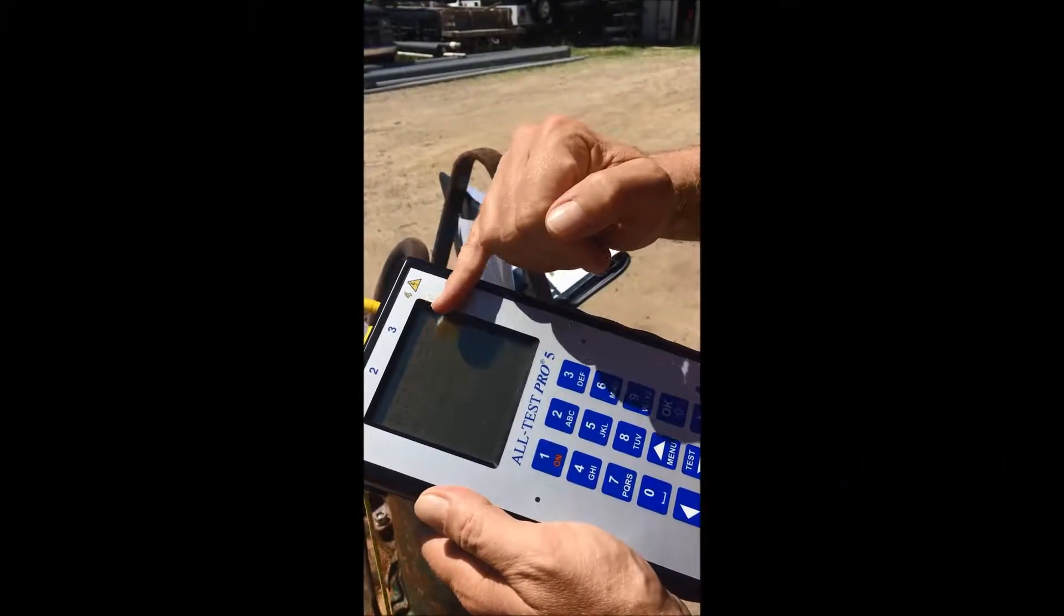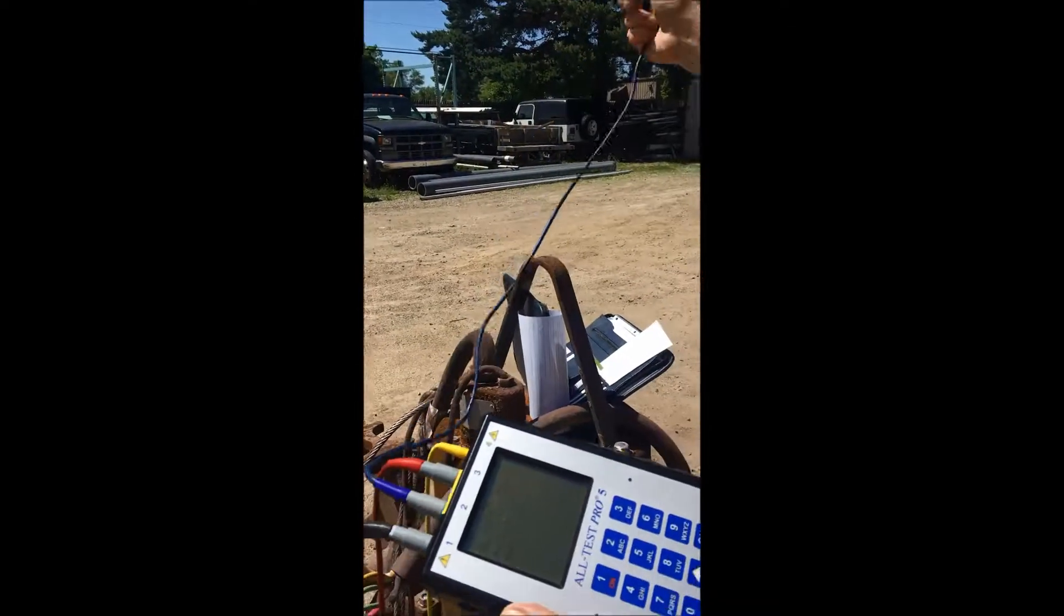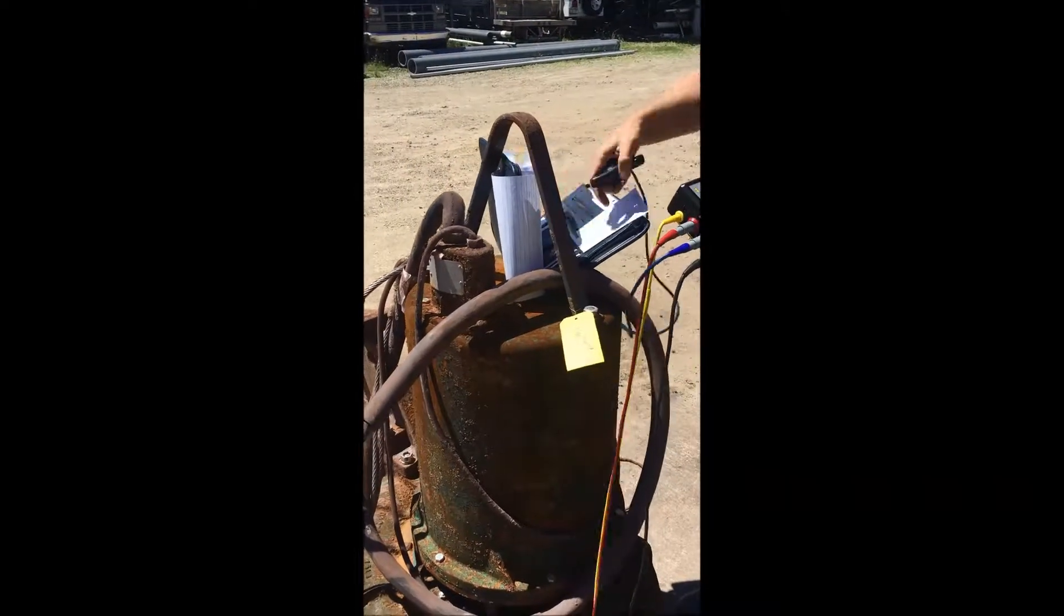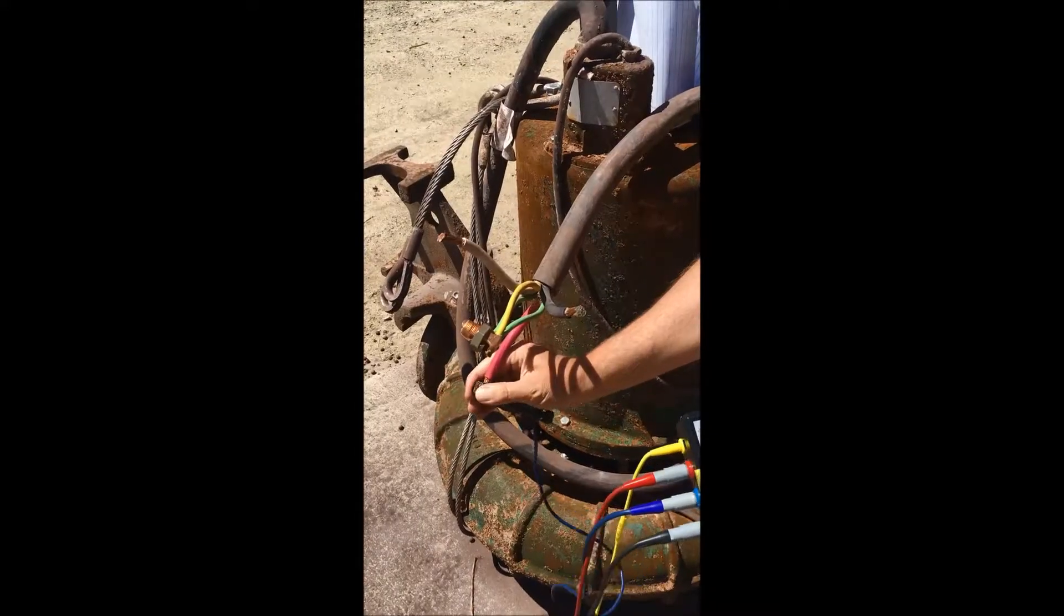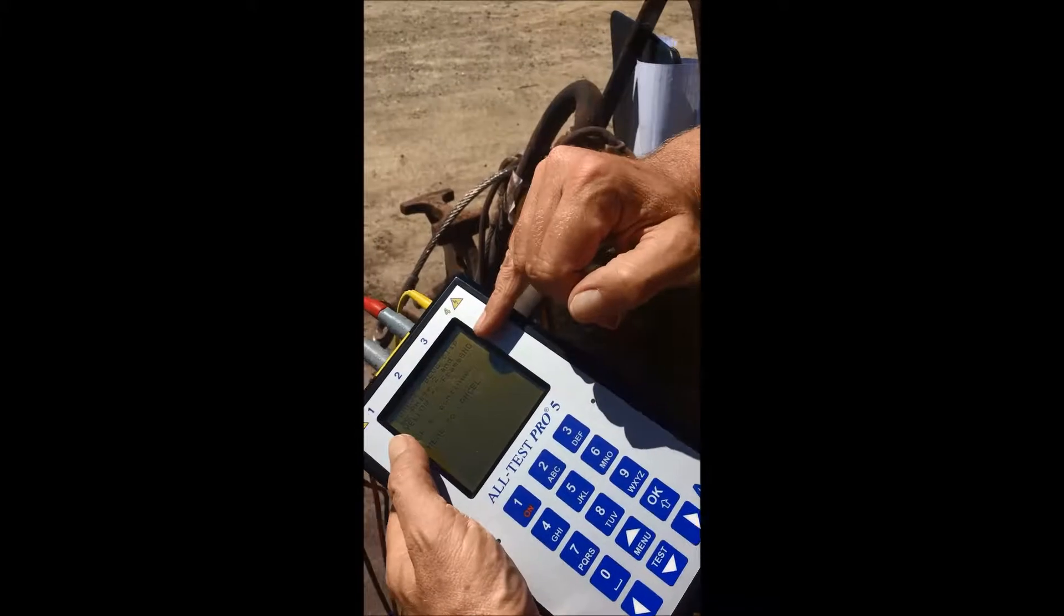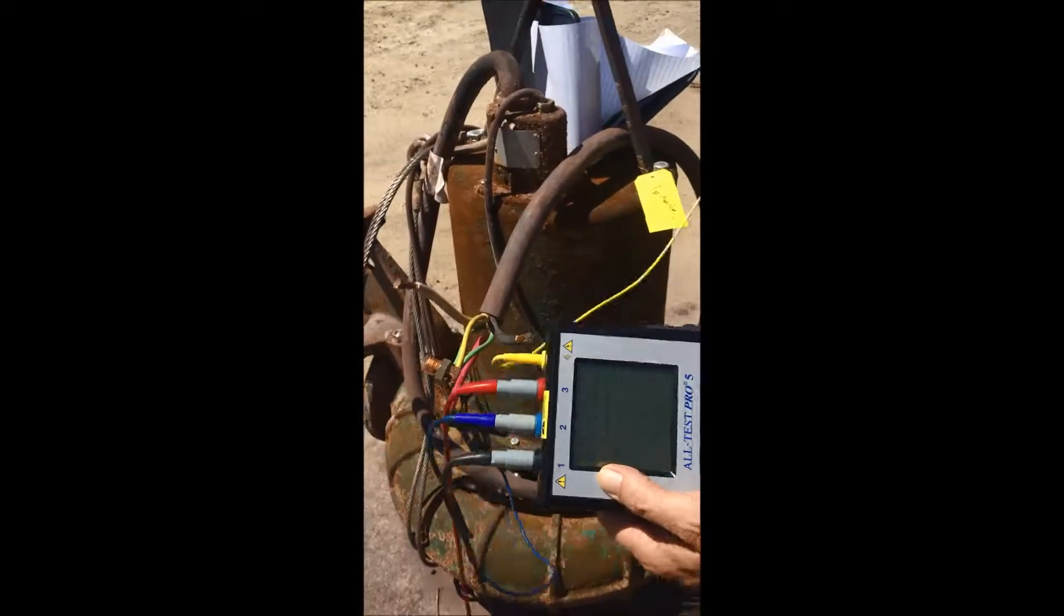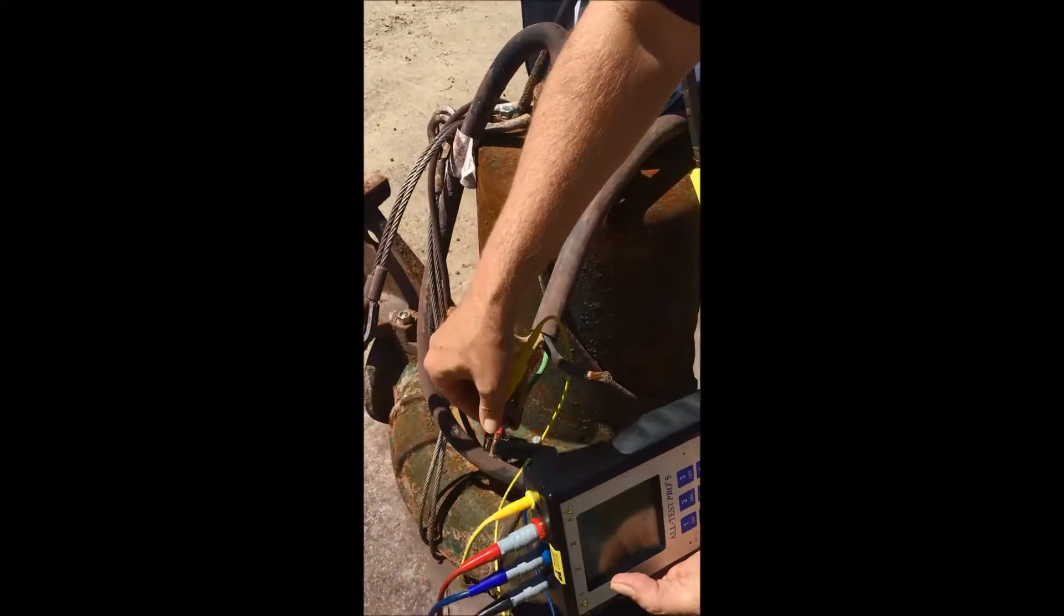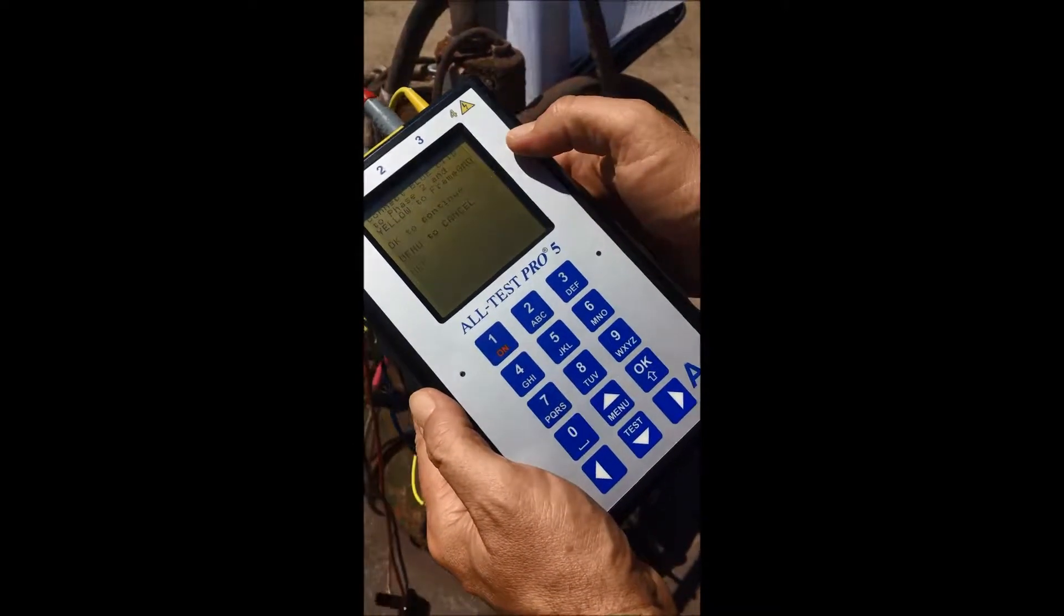It's telling us exactly what we need to do. I'm going to take our blue clip and connect it to phase two. We took a look at the wiring diagram. Phase two is our red lead. I'm going to connect blue to phase two and it tells us to connect yellow to ground or the frame. We have our ground leads all combined here. Make sure we have a good bite.